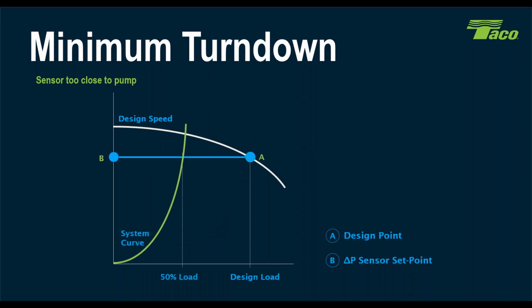Now, what's going to happen is if I get a 50% load, so my load decreases by 50%, but because of where my sensor is at, my system curve gets really, really narrowed down. So what ends up happening is at 50% load speed, my pump slows down a little bit, okay? But it actually only slows down about 20%. So you're not getting the full benefit of having that variable speed drive on there, and you're over pumping the system because you're moving more water than what the system actually requires at a 50% load point.